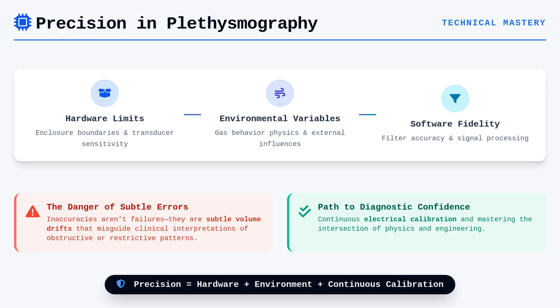Precision in plethysmography is ultimately a result of managing hardware limits and environmental variables simultaneously. The electrical calibration of these devices is not a one-time process, but a continuous requirement to ensure the transducer signals represent actual physical displacement.